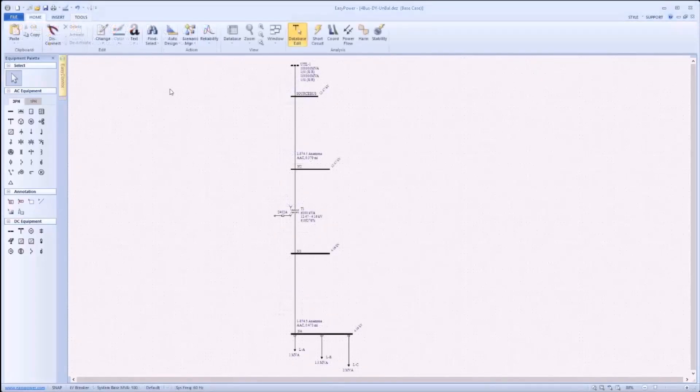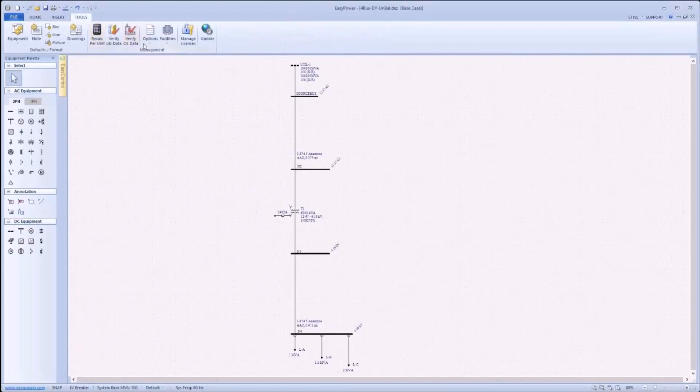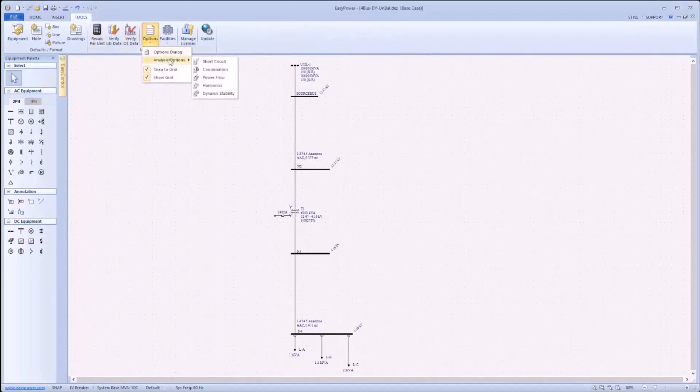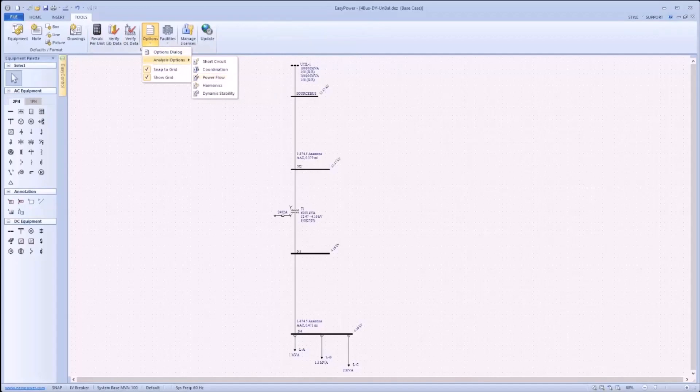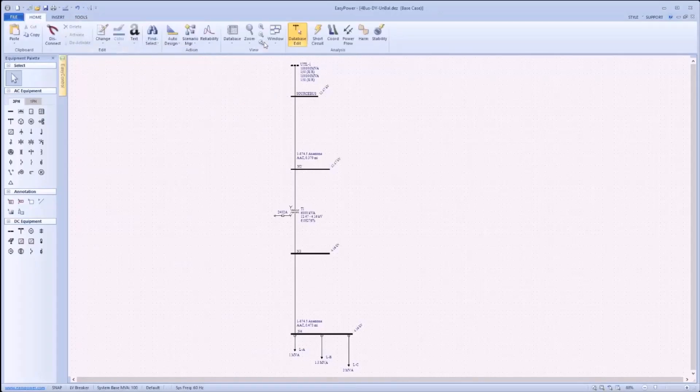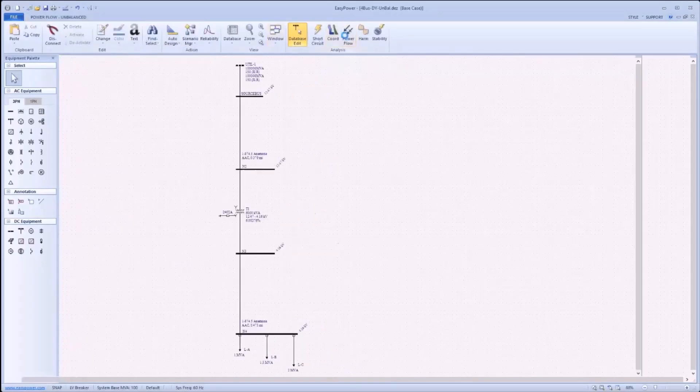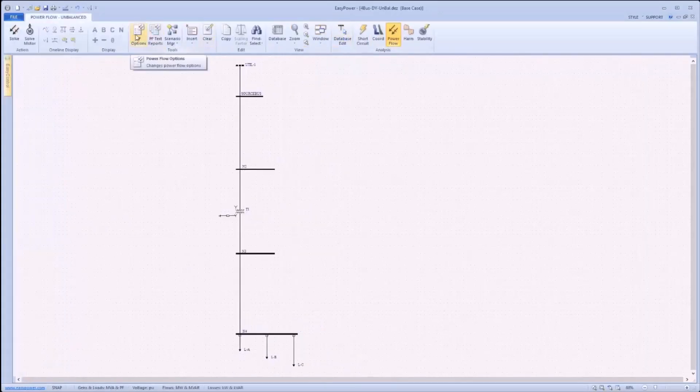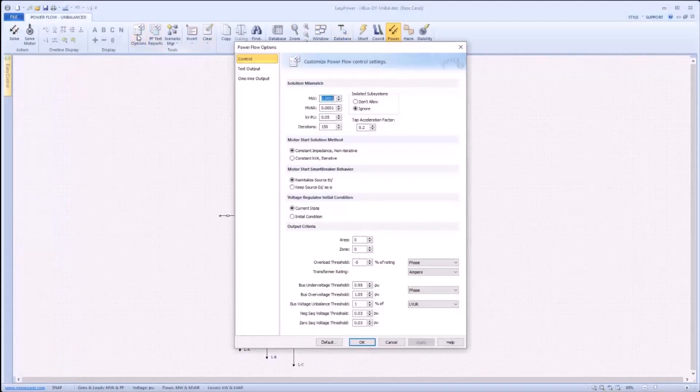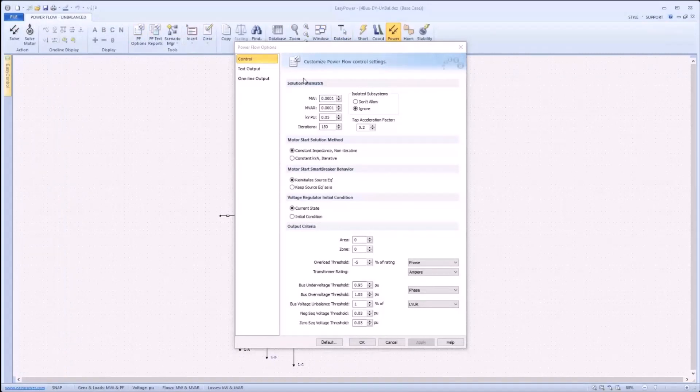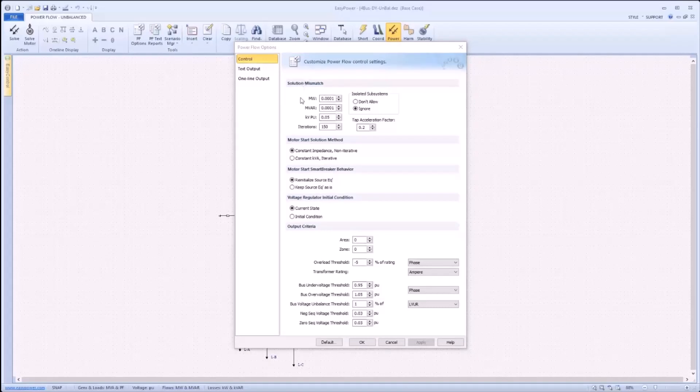To edit power flow options, users can either navigate to Tools, Options, Analysis Options within Database Edit, selecting Power Flow, or can simply enter power flow and navigate to power flow options. Once in power flow options, the control tab allows for the behavior of the power flow study to be specified. Here a user can input their desired solution mismatch limits, motor start solution method, motor start smart breaker behavior, voltage regulator initial condition, and output criteria.